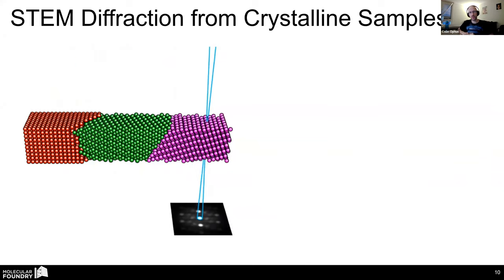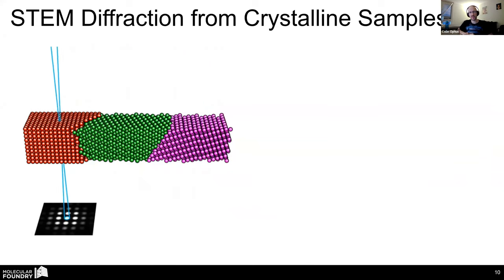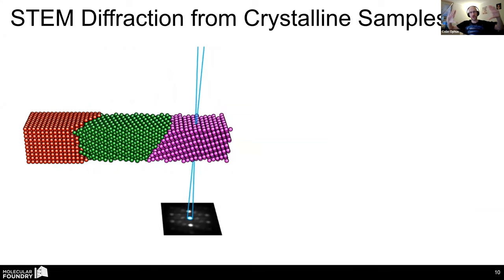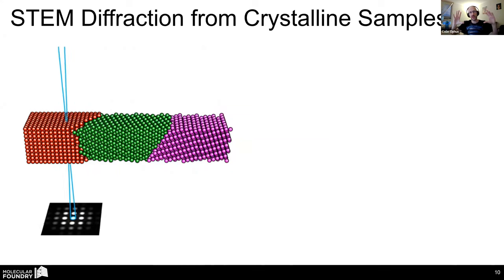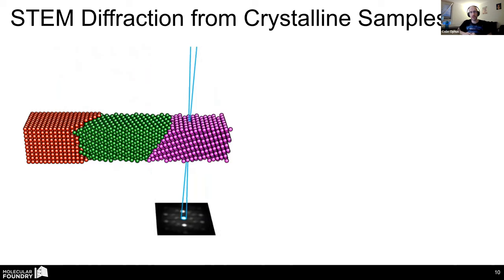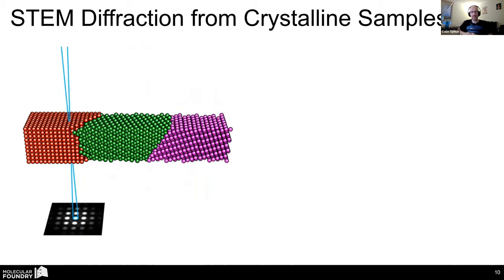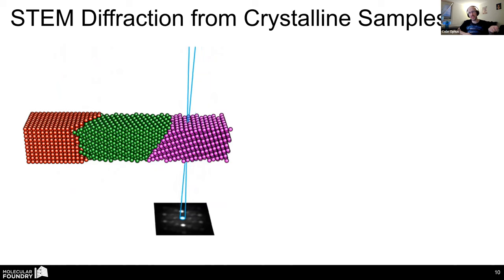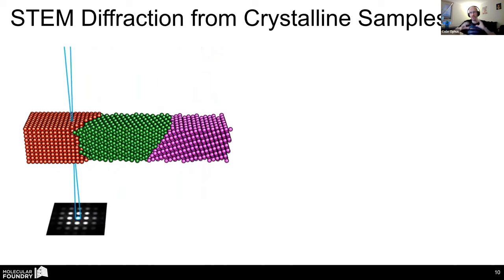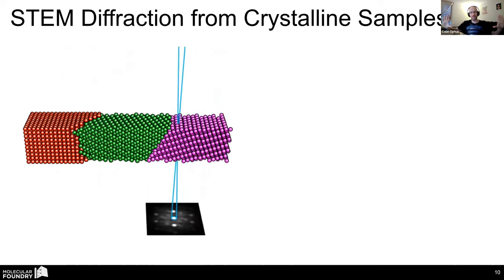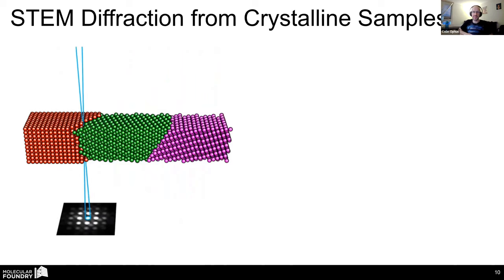So if you want atomic or subatomic resolution, you want a very large convergent semi-angle, usually on the order of 15 or 20 milliradians, and that would be the current generation of microscopes. Next generation aberration correctors will let us push it out to 30, 40, 50, maybe even 60 milliradians.